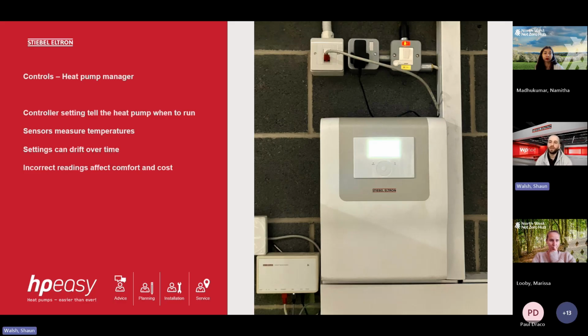So one of the other important things is the controller itself. Like I said, the whole heat pump operates as a whole system. So we have hydraulics, then we have the electrical side, and then we have the control side of things. If the controls aren't set up correctly, this can cause a lot of issues as well. So the controller's job is to tell the heat pump when to actually run. The heat pump is heavily reliant on sensors and measurements from those sensors.